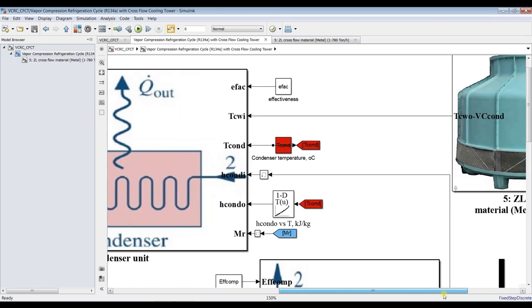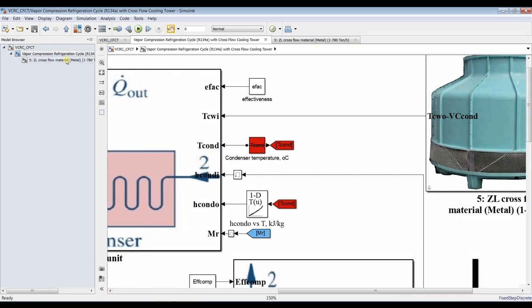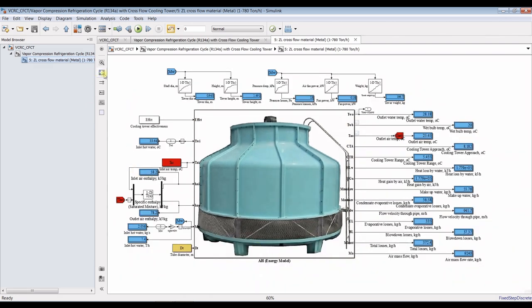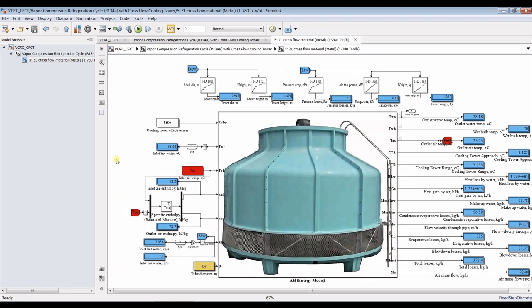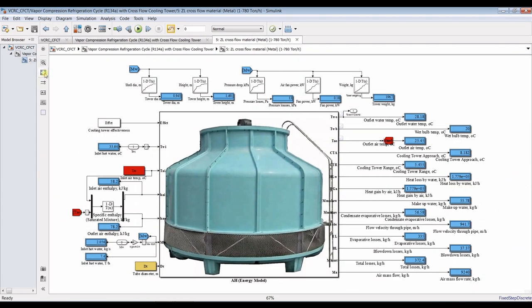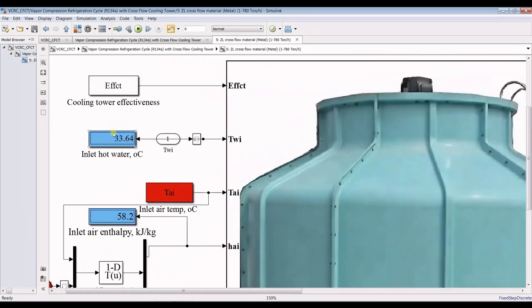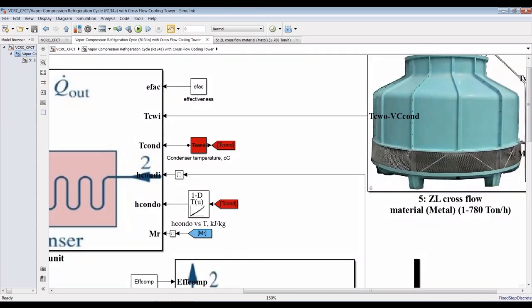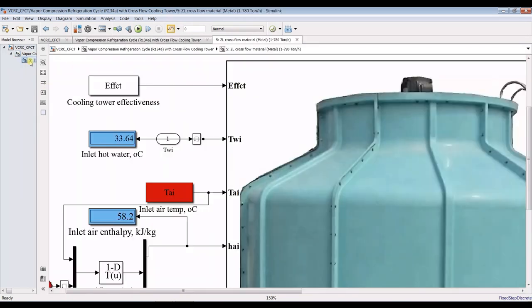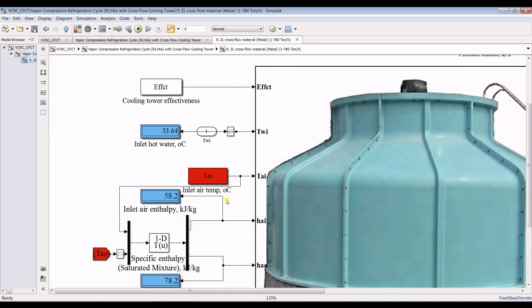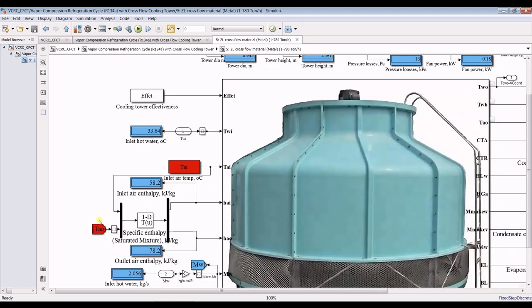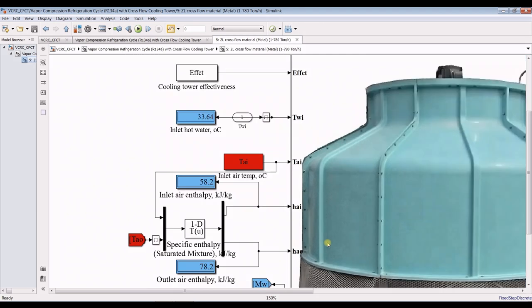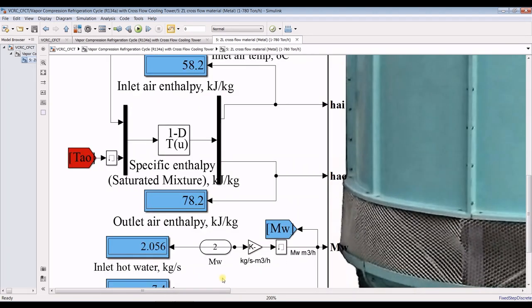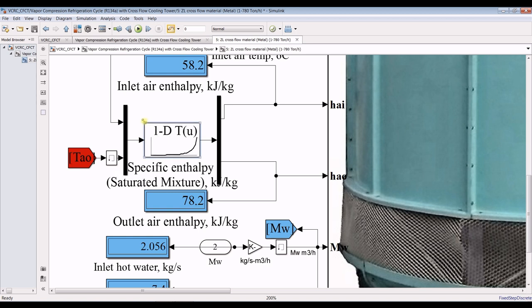So let's go inside the cooling tower and inspect what our outputs are. Let's go here. I'm sorry, let's emphasize a little bit, okay. So this is inlet water from the cooling tower, it's 33, which is output from the condenser, okay, 33.6. Outlet from the condenser is input for the cooling tower, air temperature input, and this is inlet air enthalpy, outlet air enthalpy and inlet air enthalpy. Okay, so property table of the air. Okay, you can emphasize this a little bit. Okay, a specific enthalpy of the air.